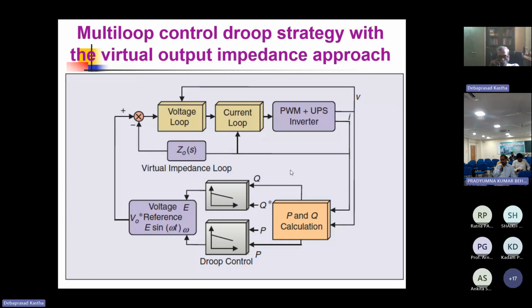See, the actual droop control is happening on the bottom side. So the input is coming from the current feedback and it is compared with the reference voltage. Now let us start from the bottom. First, you are measuring P and Q. And you have certain references from the secondary control of the P and Q. You are comparing them, and you are following a droop characteristic there itself. So that itself is telling what should be the magnitude of V0 and what should be the frequency. So you generate the reference wave E sin omega t, where both E and omega are variable. On top of that, you are providing a virtual impedance.